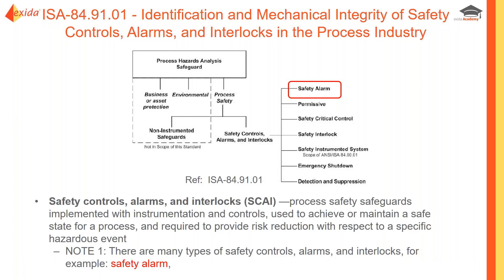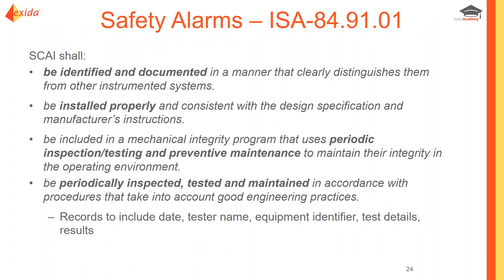ISA 84.91.01 relates to the mechanical integrity of a grouping of functions called Safety Controls, Alarms, and Interlocks. Its definition covers process safety safeguards implemented within instrumentation and control — not mechanical safeguards — used to maintain a safe state, focusing primarily on preventive safeguards requiring a level of risk reduction. The primary contribution of this standard to safety alarms relates to periodic testing and maintenance as part of an overall mechanical integrity program.